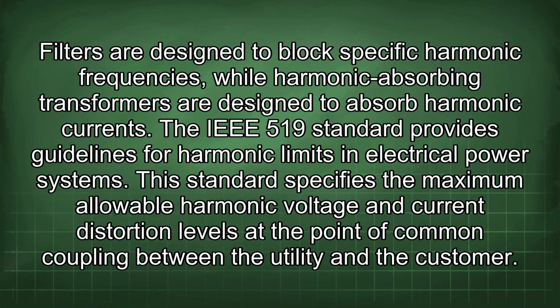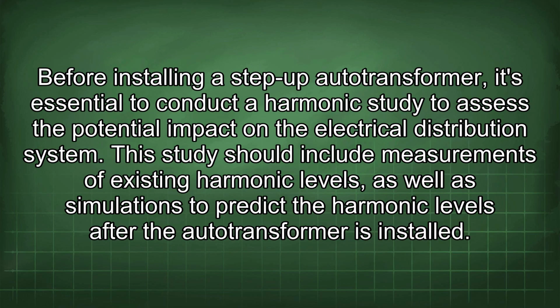The IEEE 519 standard provides guidelines for harmonic limits in electrical power systems. This standard specifies the maximum allowable harmonic voltage and current distortion levels at the point of common coupling between the utility and the customer. Before installing a step-up autotransformer, it's essential to conduct a harmonic study to assess the potential impact on the electrical distribution system.